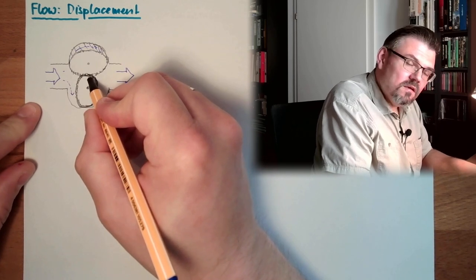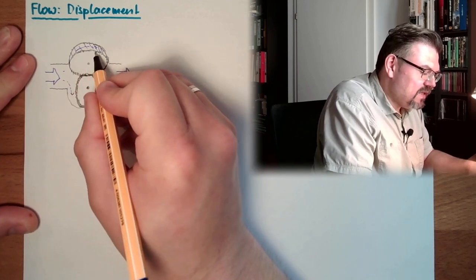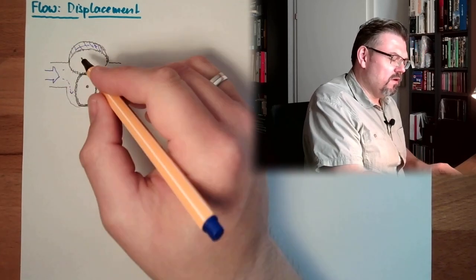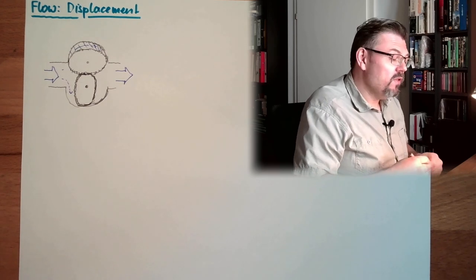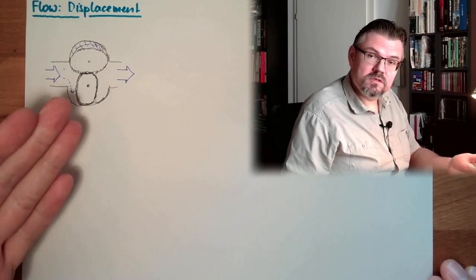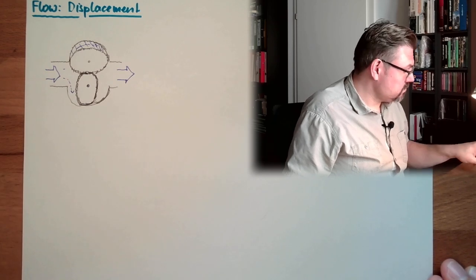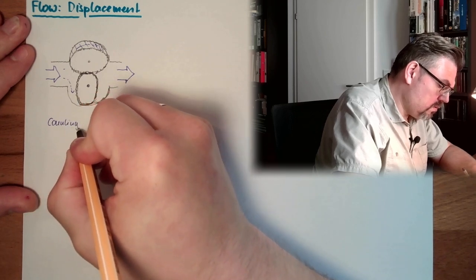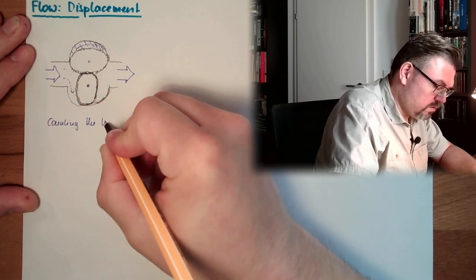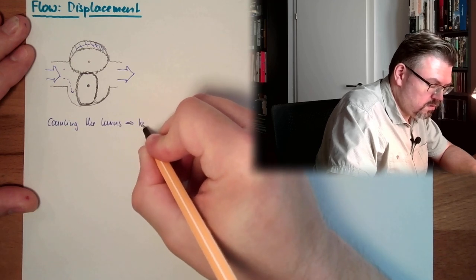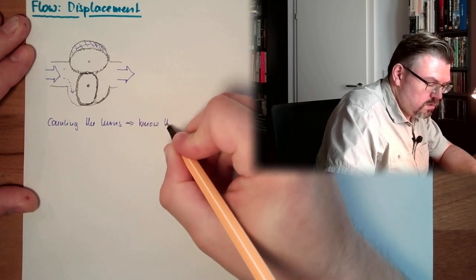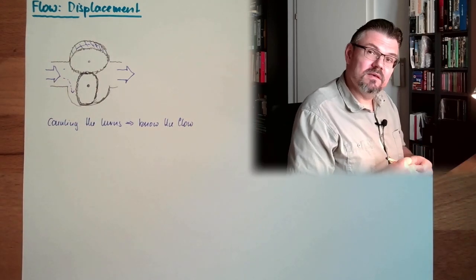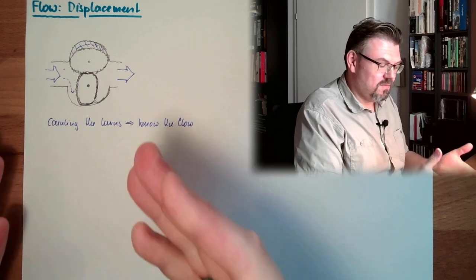Here we are sealed. Here we are sealed, and we are always passing this amount of liquid. With every turn, we are passing this amount of liquid on the upper side and on the lower side, and so we only have to count the turns. So counting the turns, we know the flow. We exactly know how much volume has passed. It's easy, right?